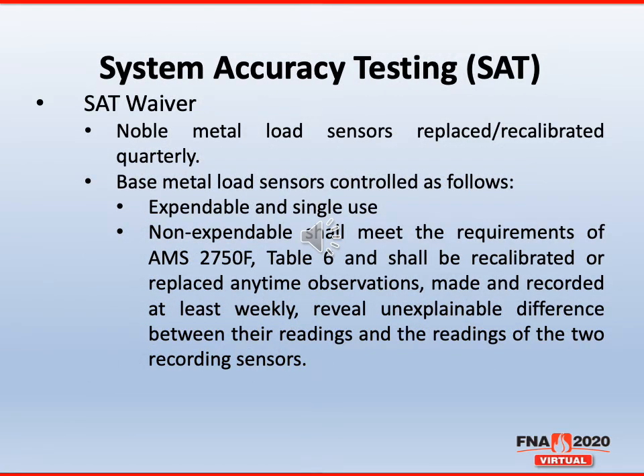There have been some slight changes to the SAT waiver option. Noble metal load thermocouples shall be replaced or recalibrated on a quarterly basis. When base metal load sensors are used, they shall be controlled as follows. If they're expendable load thermocouples, they are limited to a single use. If they're non-expendable, they shall meet the requirements of AMS 2750F Table 6 and shall be recalibrated or replaced anytime observations, recorded on a weekly basis, reveal any unexplainable difference between their readings and the readings of the two recording sensors.